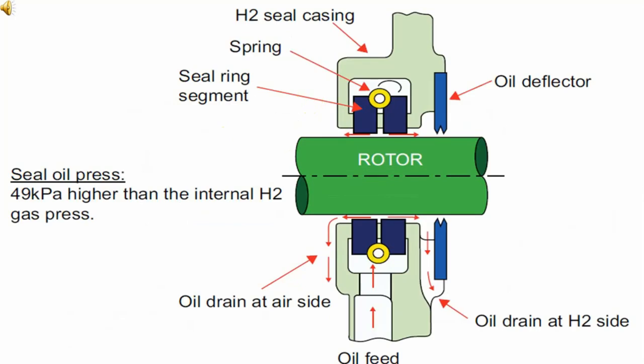Here is the same diagram but a little bigger in size. We can see the hydrogen seal casing, the seal segment, and the seal ring segment. In the casing, oil is being fed. The oil then comes out from this place, forming a thin film. One part of the oil is going to the air side and the other part is going to the hydrogen side.